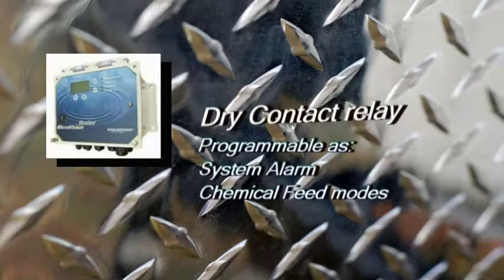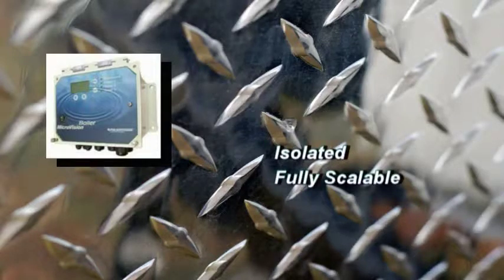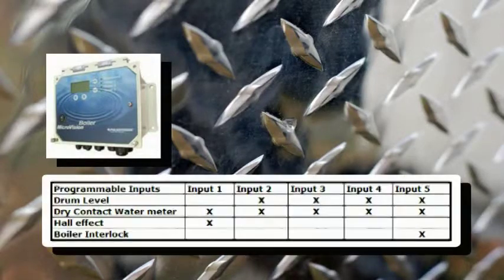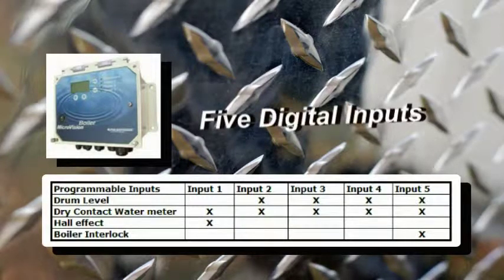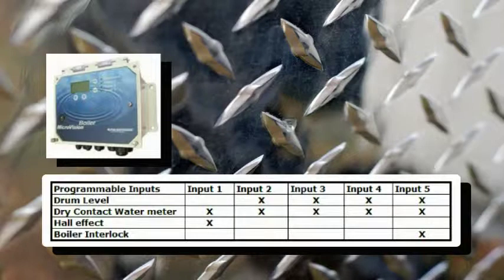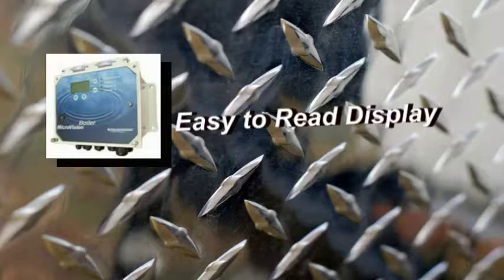The controller has a dry contact relay for remote alarm conditions. And of course, a standard feature is a 4 to 20 milliamp output for accurate reporting of the conductivity levels. There are a total of 5 digital inputs that can be configured as water meters, drum levels, or boiler interlock. And the large graphical display shows the information that you need to see.